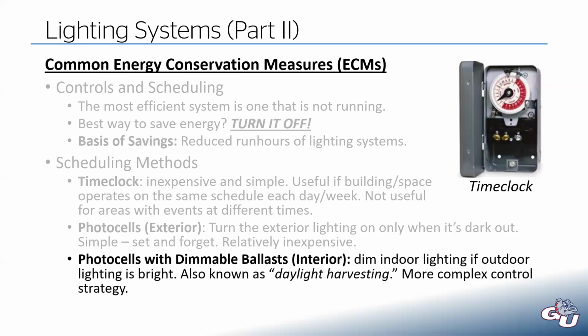To take this a step further, you could buy photocells that have dimmable ballasts, and that would be for fluorescent lighting. I suppose you could use this to control LEDs as well, which wouldn't have ballast. But this is using a similar idea, but on interior light fixtures inside your building. You still have that photocell that detects how much light you have inside, and it will dim your indoor lights if you're getting a lot of outdoor lighting coming through the windows. Another term for this is daylight harvesting.